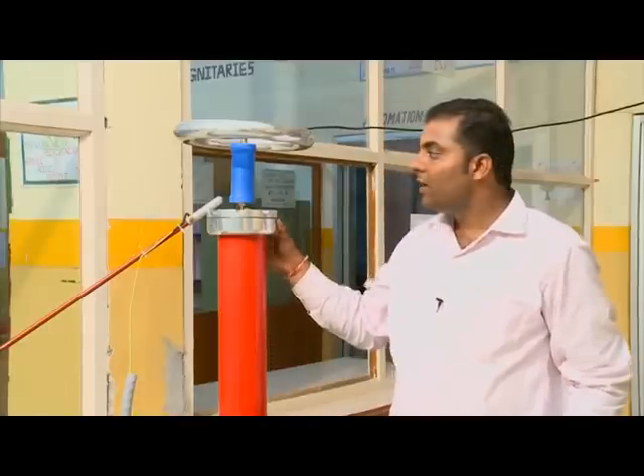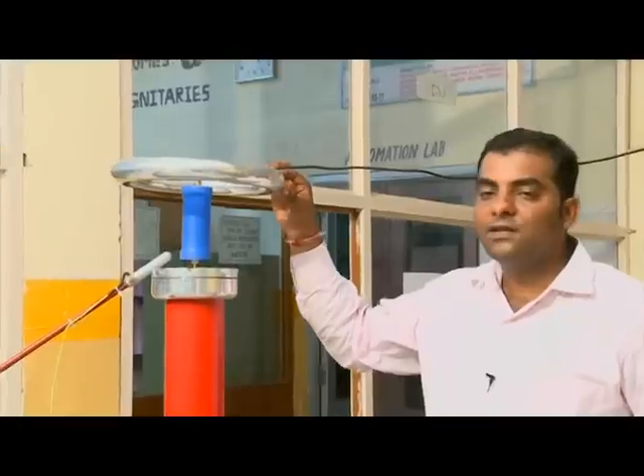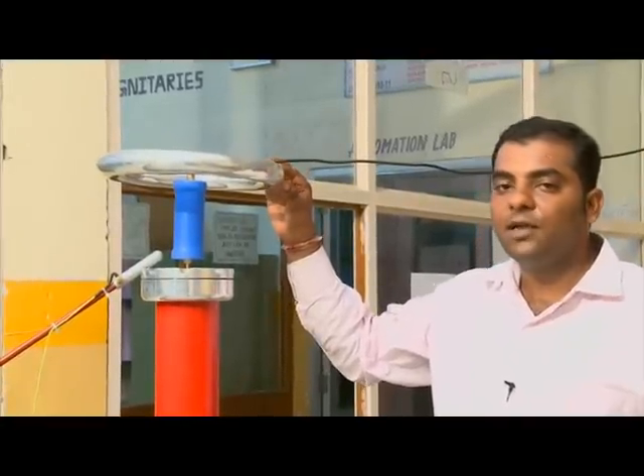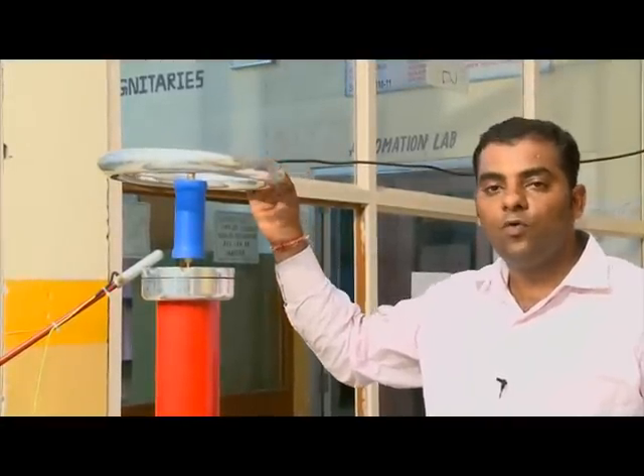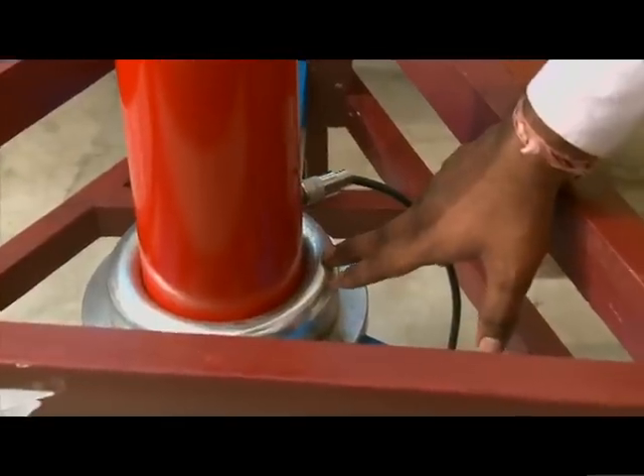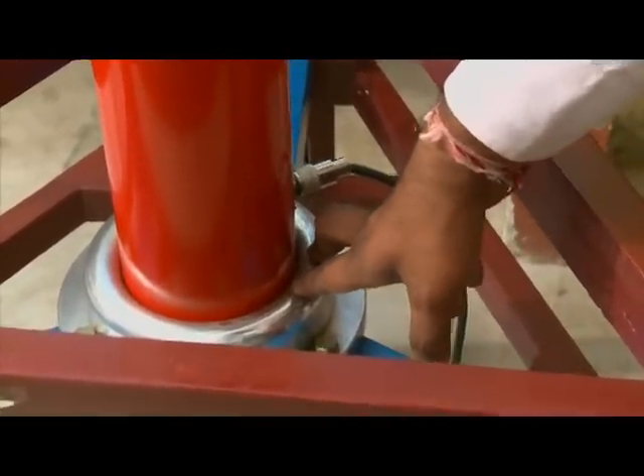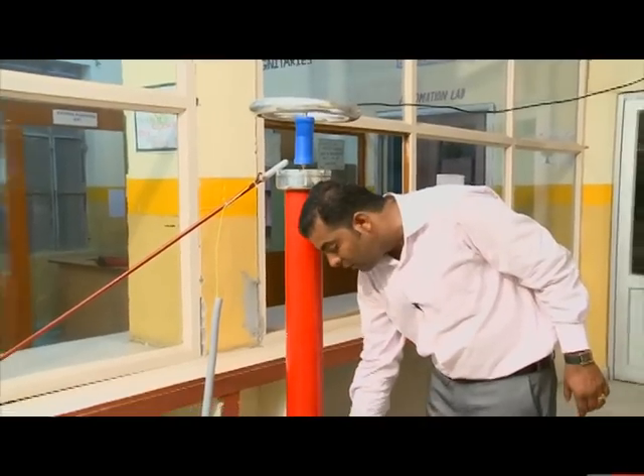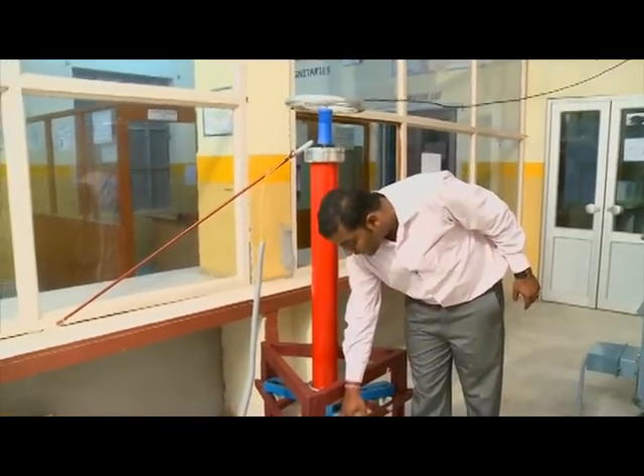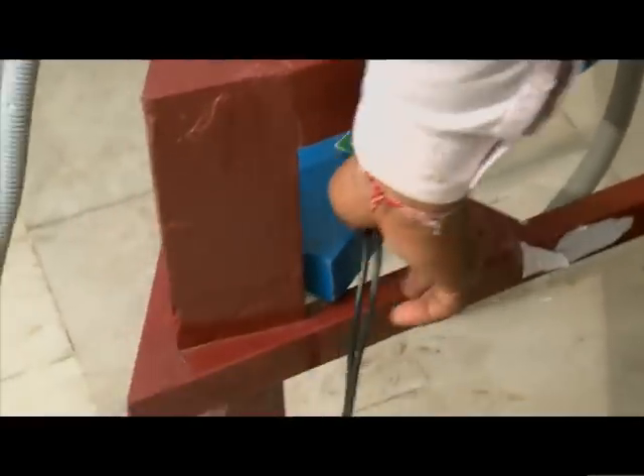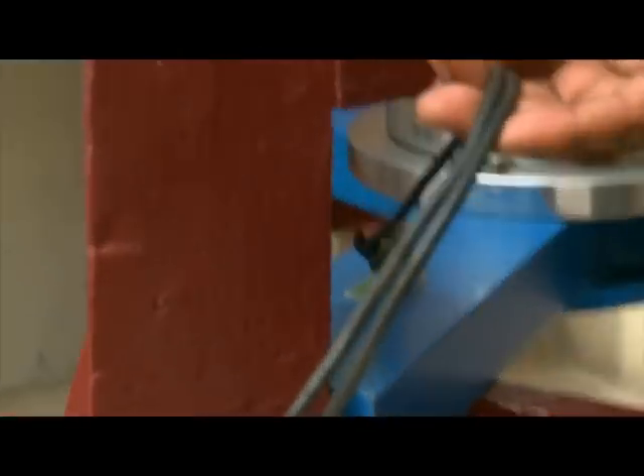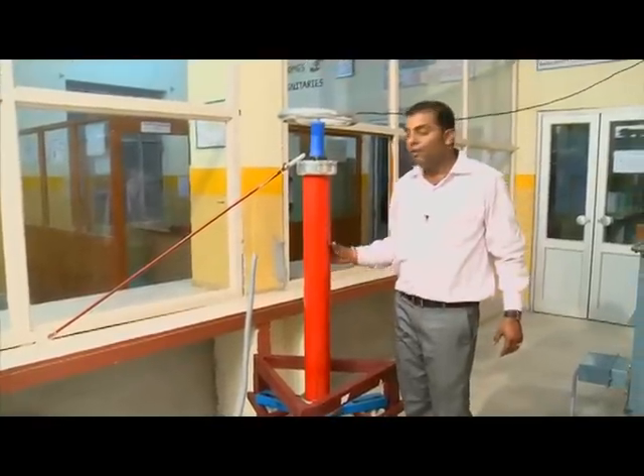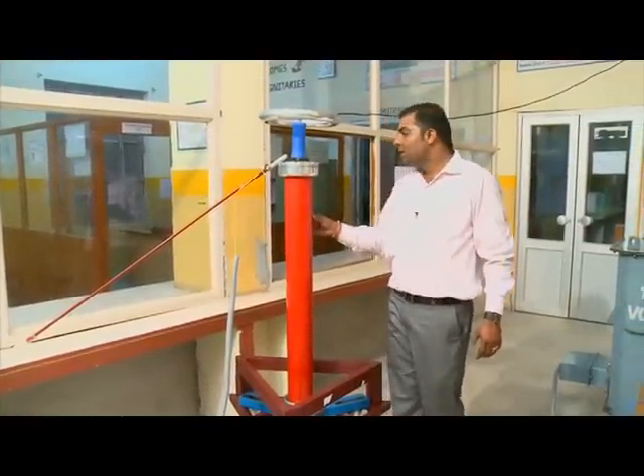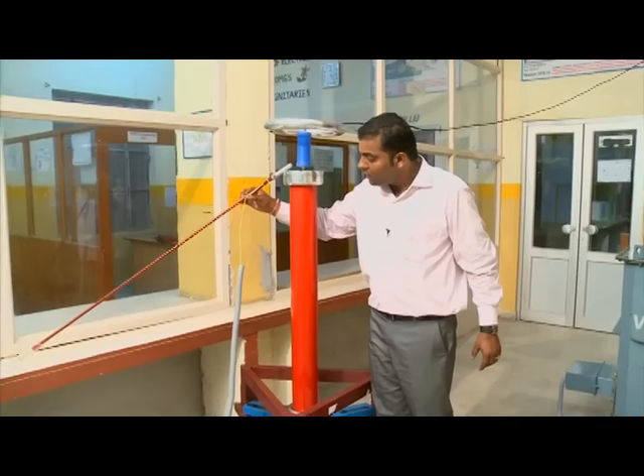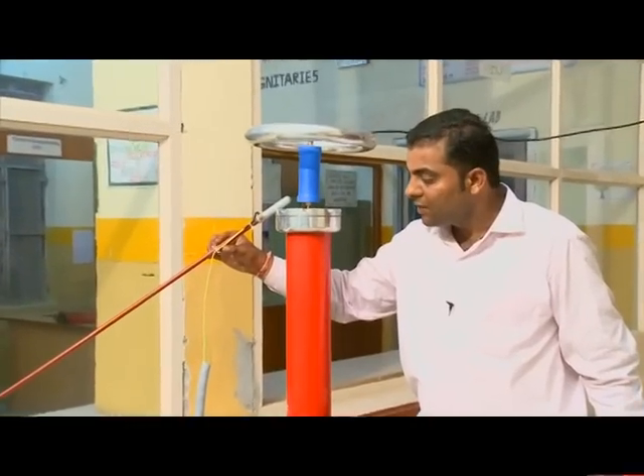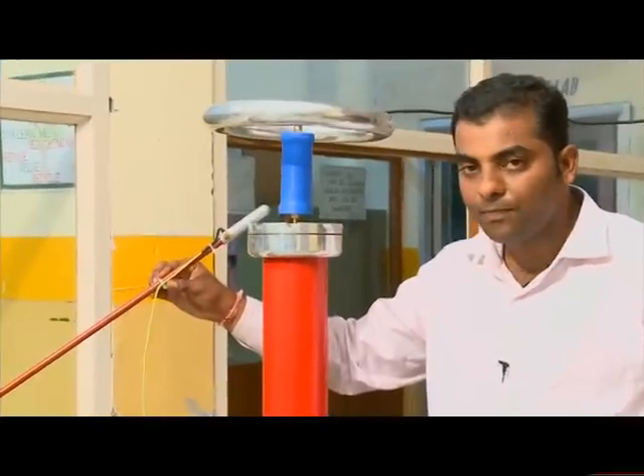In that capacitance divider, this is the HV terminal which is highly polished, and the value of this HV terminal is 100 picofarad. And this is the LV terminal of this capacitance divider, and the value of this LV terminal is 0.1 microfarad. This LV terminal is connected with the control panel. With the help of the control panel, we will observe the value of transmitted voltage. This is the earthing rod to earth the complete setup of capacitance divider for the protection scheme.